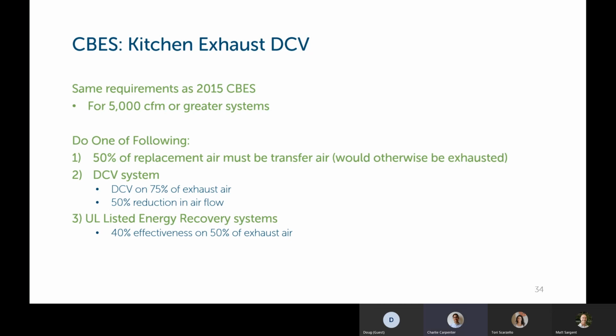And the last strategy here is a UL listed energy recovery system within the hood itself, and it needs to be 40% effectiveness and similarly be installed on at least 50% of the kitchen exhaust air. So not every hood, but at least 50% of the volume of air.